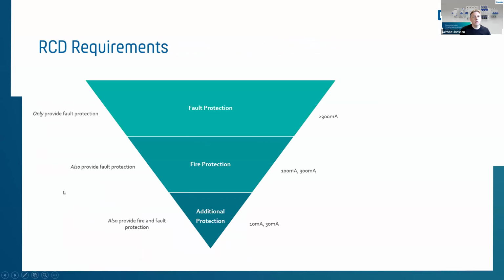Yeah, what are the requirements put up to an RCCB? The main requirement is fault protection. And if you have the different RCCBs with different tripping characteristics and residual current tripping thresholds, if we exceed 300 milliamp of residual current, there's only fault protection guaranteed. There is no fire protection or even more being available with such a device.